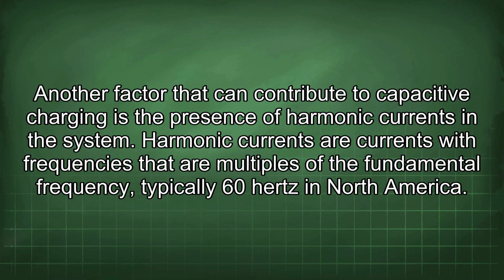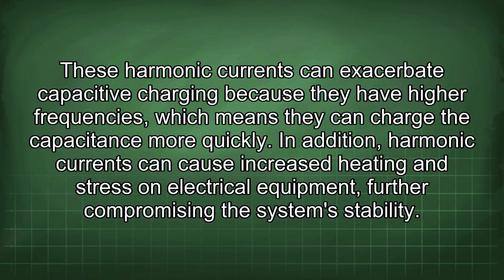Another factor that can contribute to capacitive charging is the presence of harmonic currents in the system. Harmonic currents are currents with frequencies that are multiples of the fundamental frequency, typically 60 Hz in North America. These harmonic currents can exacerbate capacitive charging because they have higher frequencies, which means they can charge the capacitance more quickly. In addition, harmonic currents can cause increased heating and stress on electrical equipment, further compromising the system's stability.